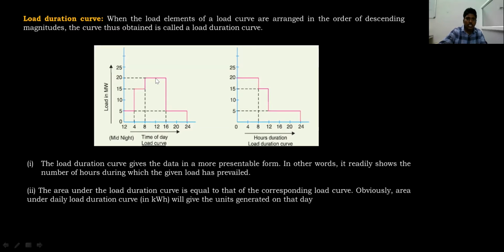And the next highest load is 15 megawatts. For what time is 15 megawatts there? 15 megawatts is there from 8 to 12, which gives you 4 hours. For those 4 hours the load is 15 megawatts. In the same way, in descending order, we ask what is the maximum load? We need to first plot that in the load duration curve, and the next highest maximum demand you need to plot next.